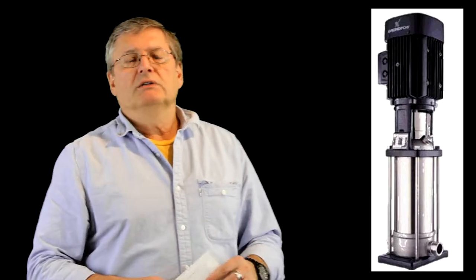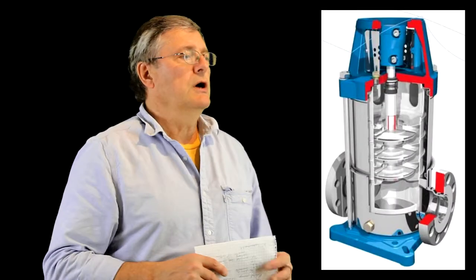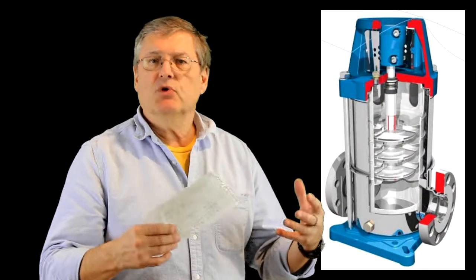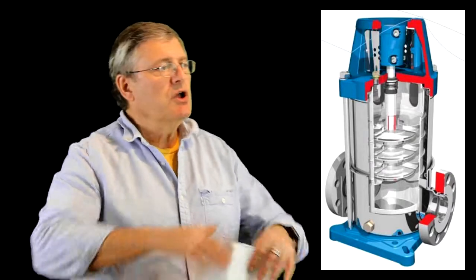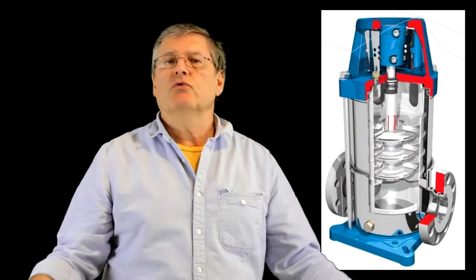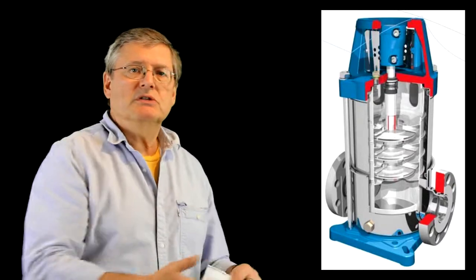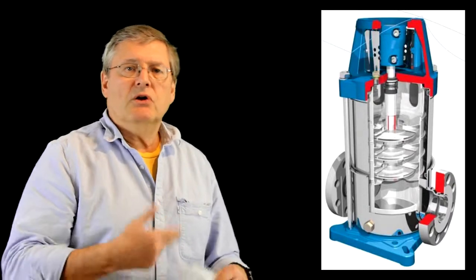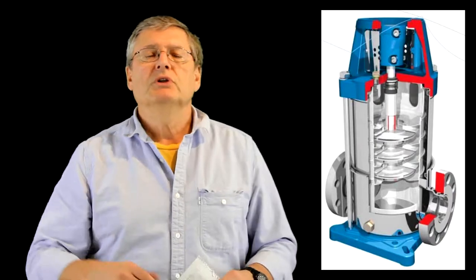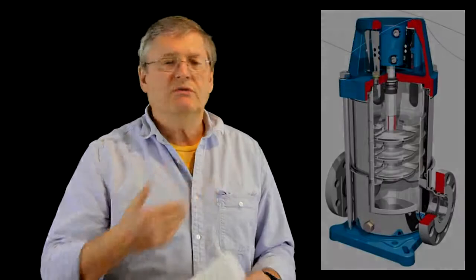Used in a variety of situations. I've seen it used for, let's say, in a fire main system where you need to maintain the pressure. If you have a huge system that's distributed all over the place you'll always have leaks where you lose the pressure. These little guys can be installed somewhere in the system and start automatically to boost up the pressure, and in any application where you need to raise the pressure for a given service.